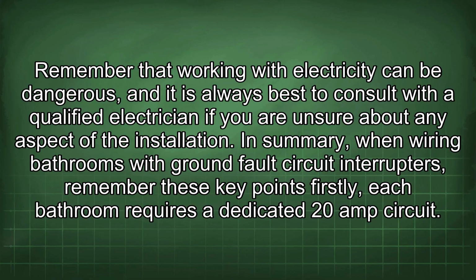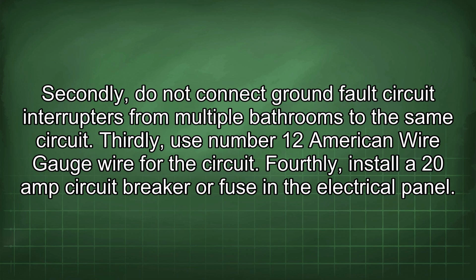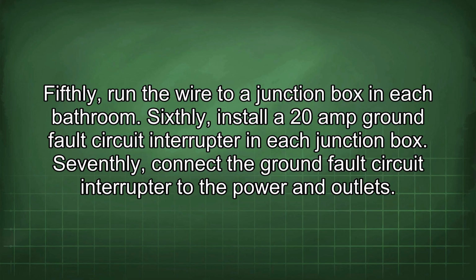Firstly, each bathroom requires a dedicated 20 amp circuit. Secondly, do not connect ground fault circuit interrupters from multiple bathrooms to the same circuit. Thirdly, use number 12 American wire gauge wire for the circuit. Fourthly, install a 20 amp circuit breaker or fuse in the electrical panel. Fifthly, run the wire to a junction box in each bathroom. Sixthly, install a 20 amp ground fault circuit interrupter in each junction box. Seventhly, connect the ground fault circuit interrupter to the power and outlets.